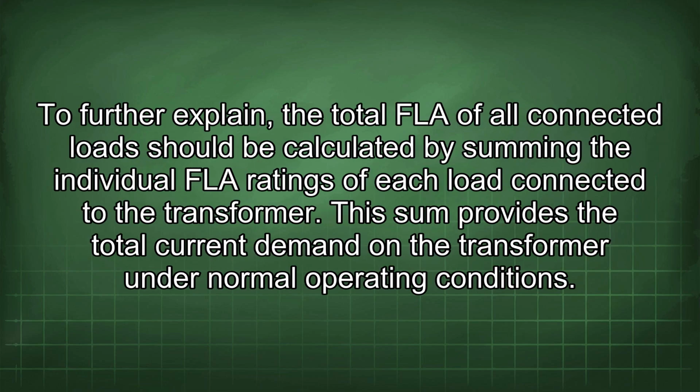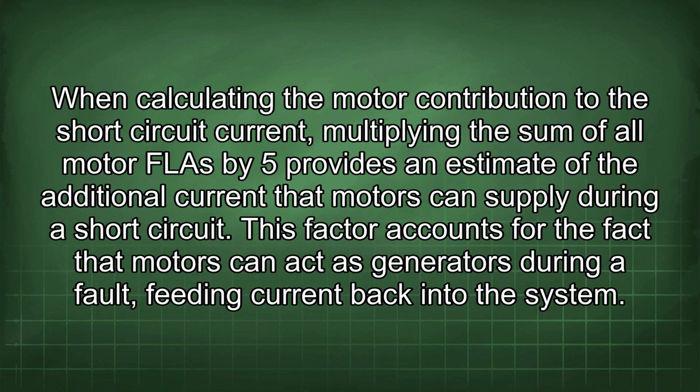To further explain, the total FLA of all connected loads should be calculated by summing the individual FLA ratings of each load connected to the transformer. This sum provides the total current demand on the transformer under normal operating conditions. When calculating the motor contribution to the short-circuit current, multiplying the sum of all motor FLA by 5 provides an estimate of the additional current that motors can supply during a short circuit.